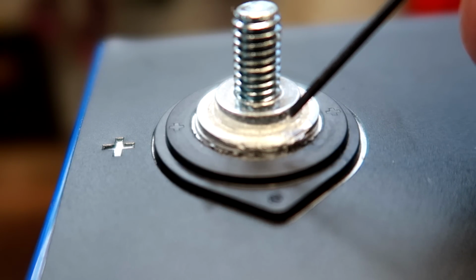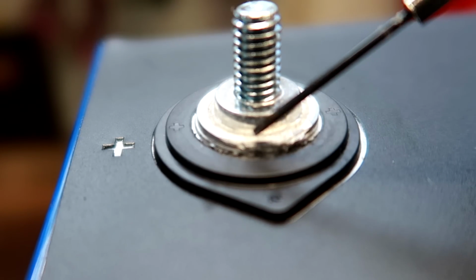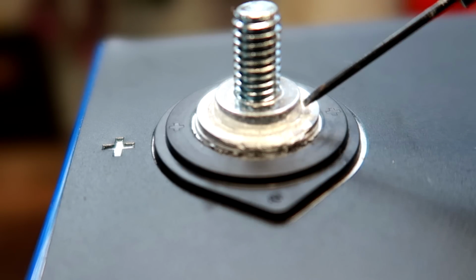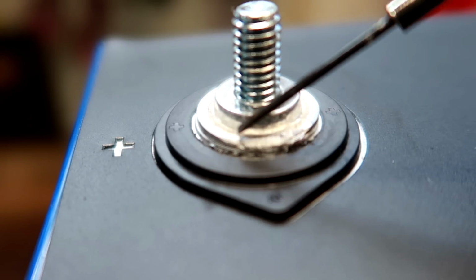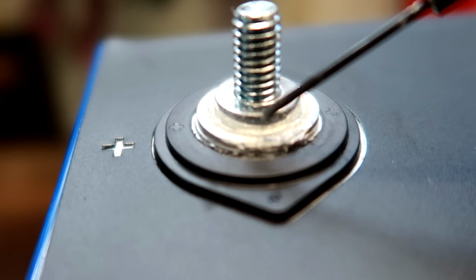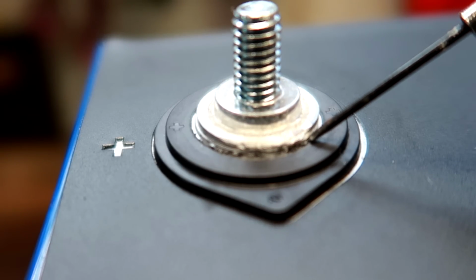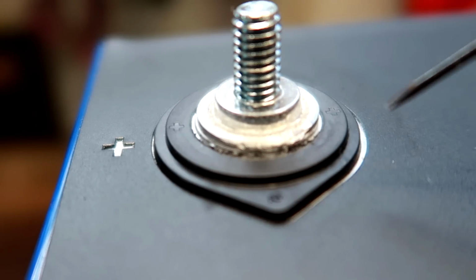And of course, adding a copper washer here will also increase the resistance, because we're adding another layer around this terminal. There are more points of connection, which means higher resistance from the terminal down here to the bus bar sitting up here.